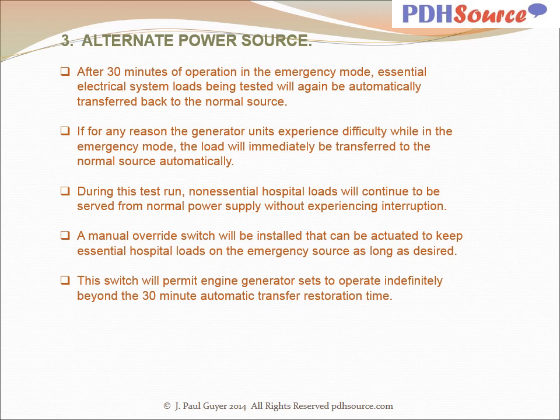A manual override switch will be installed that can be actuated to keep essential hospital loads on the emergency source as long as desired. This switch will permit engine generator sets to operate indefinitely beyond the 30-minute automatic transfer restoration time.